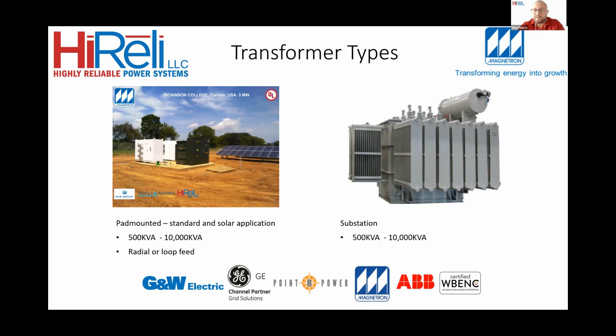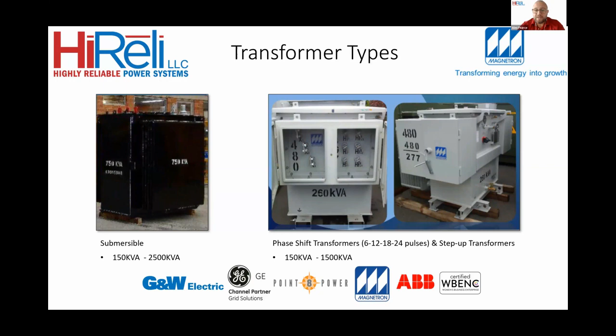Submersible applications, 150 kVA to 2,500 kVA is the wheelhouse for submersible applications if you have to go underground. And then for phase shift and step up transformers, which is their oil and gas kind of pumping application, which I'll touch on in a few slides. They provide both those, 150 kVA to 1,500 kVA as well. So getting into the standard features and options.